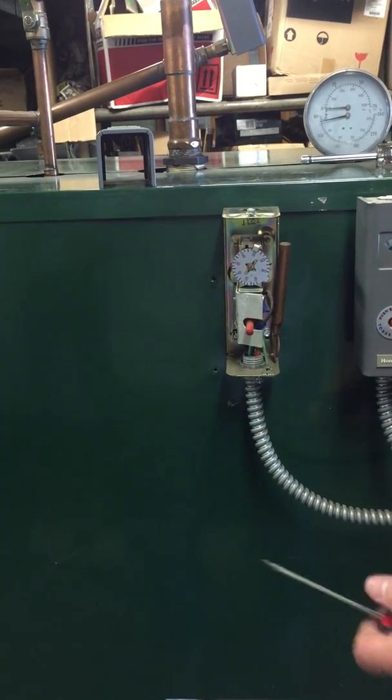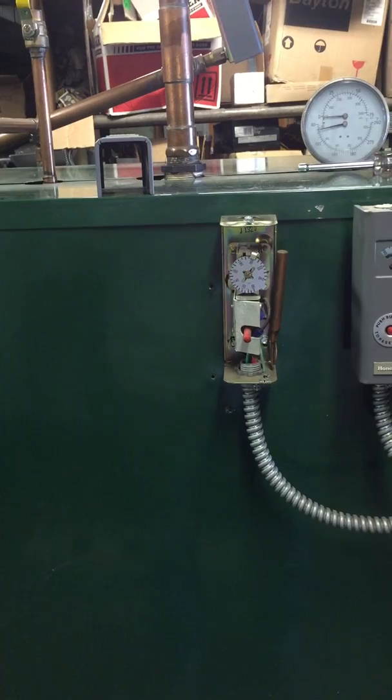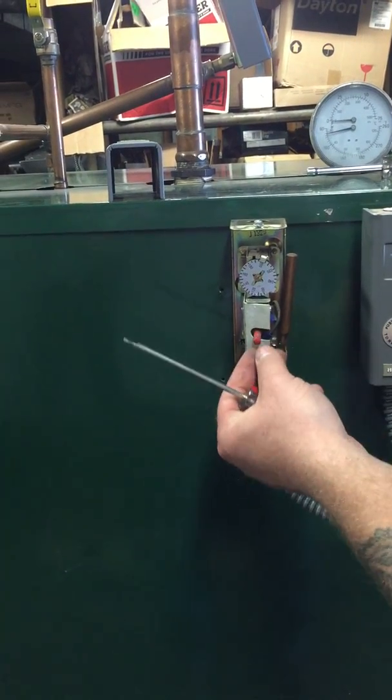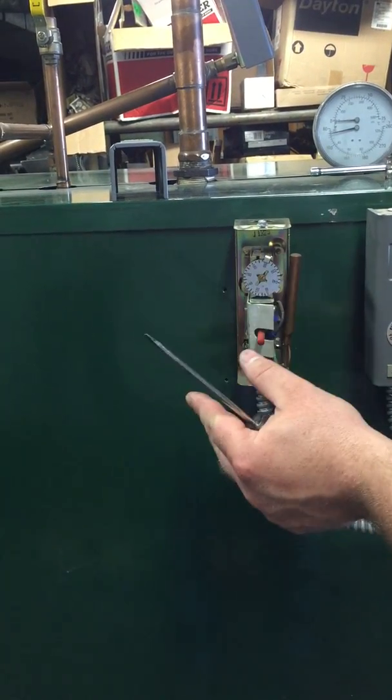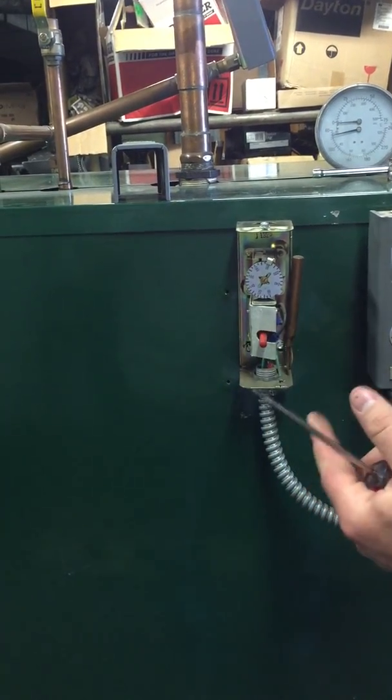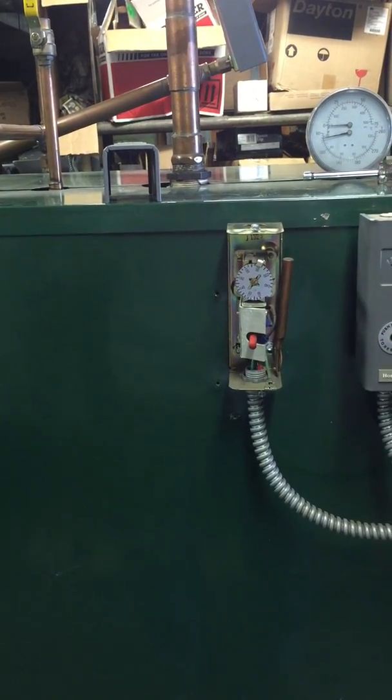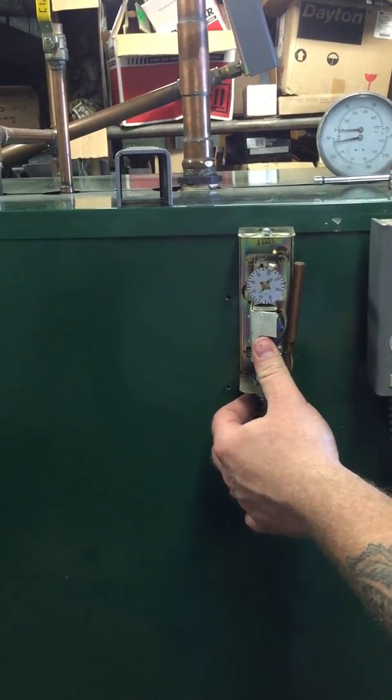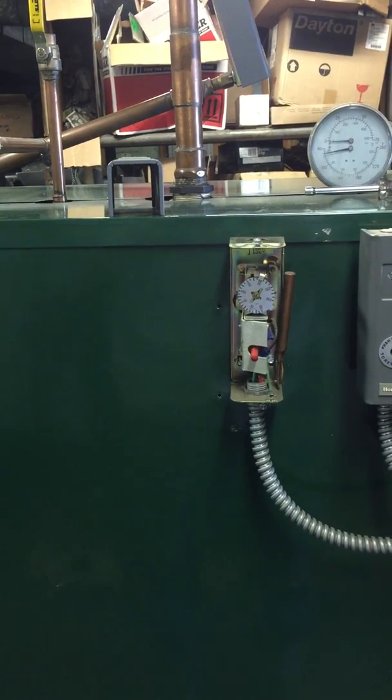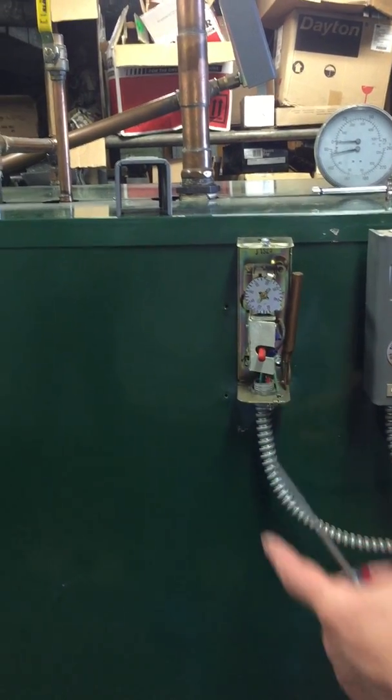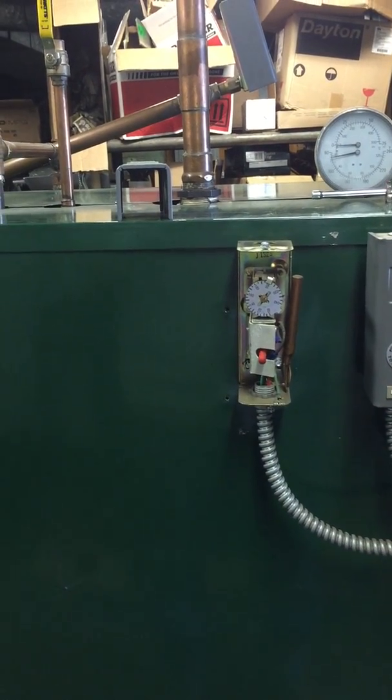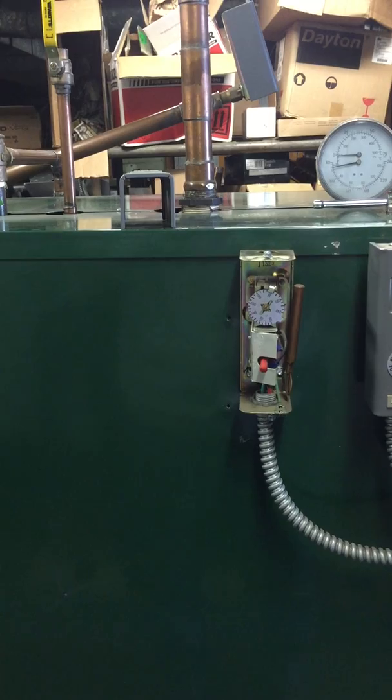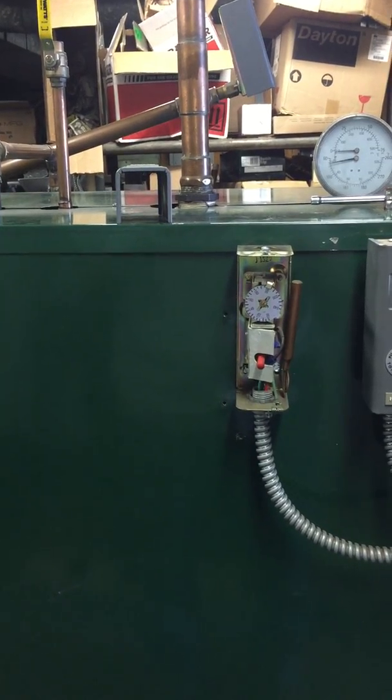is if this boiler ever hits the 195 degree mark, it'll reset and go out on hard lockout where you've got to manually come down and reset. What that means is these two control the combustion—the primary motor and the secondary combustion motor—and it will shut them down.